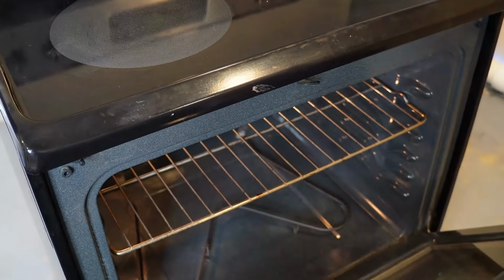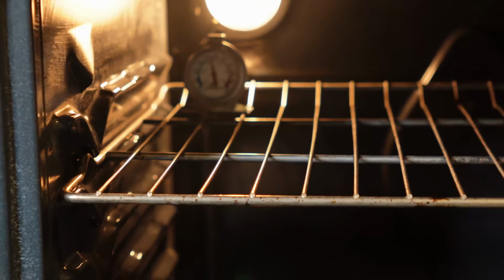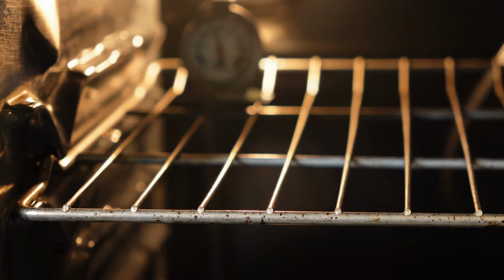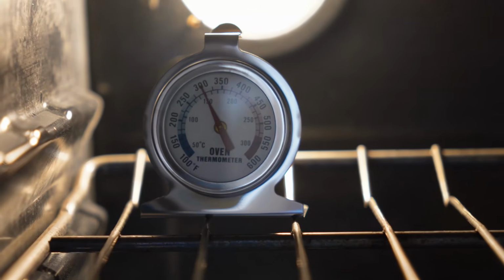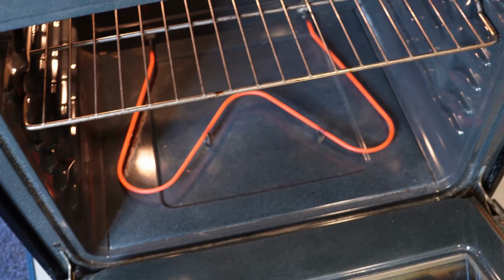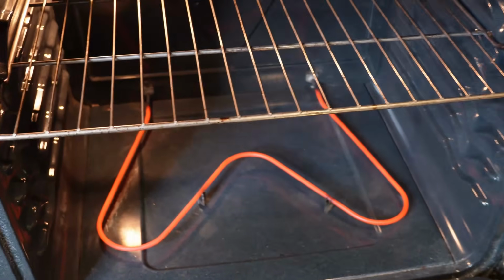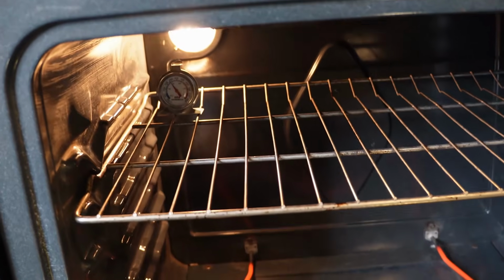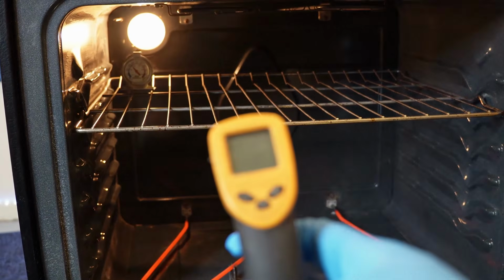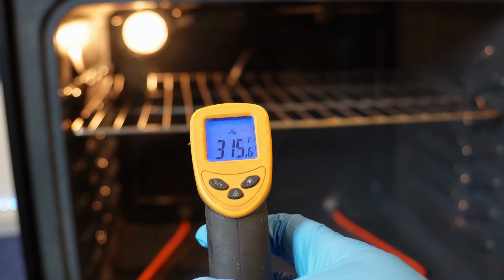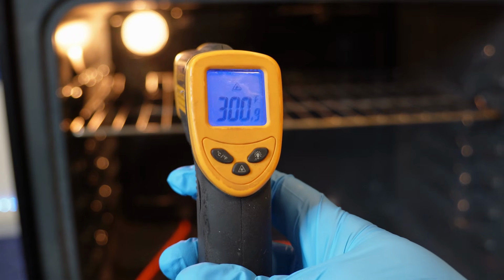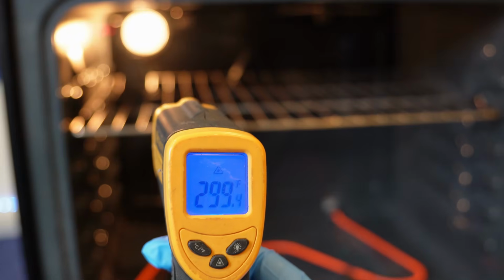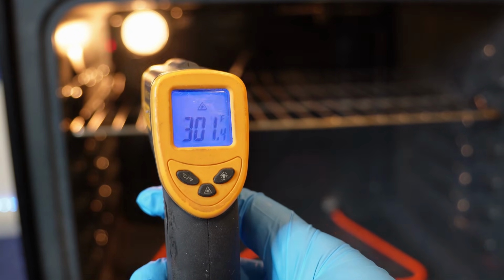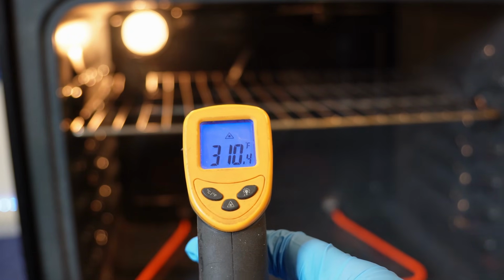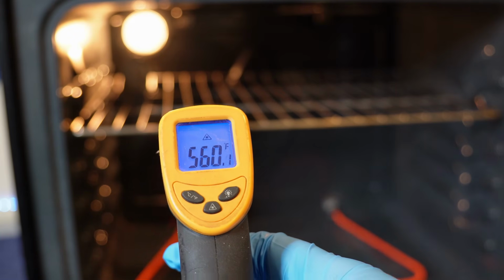And here we are at 20 minutes. This is why you want to use the thermometer rather than the gun. It's only at 300 degrees so far, but it's still rising. We don't want to call it off just yet, so let's give it another 10 minutes. You can see that the element here is running. We definitely don't want to take a reading while it's still trying to raise the temperature. While we wait, you can see that the cabinet temperature varies quite a bit from 295 degrees up to about 330. Although the thermal gun can theoretically work in the right location, the meat thermometer gives us a better long-term reading with the door closed.